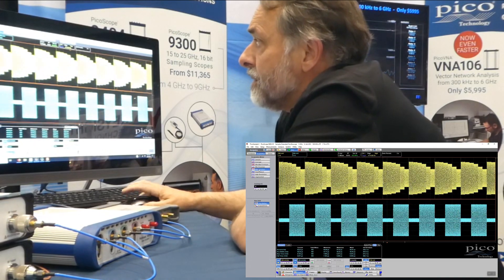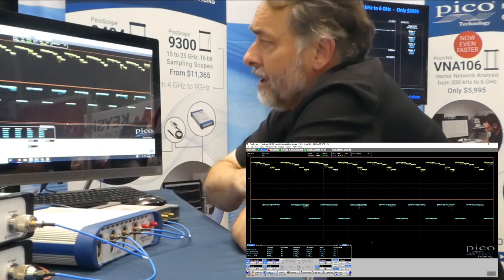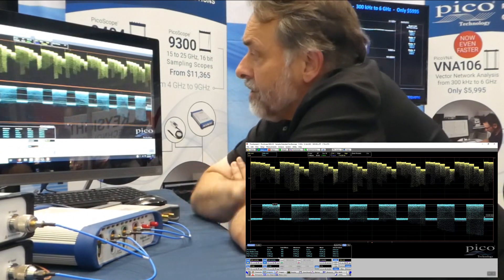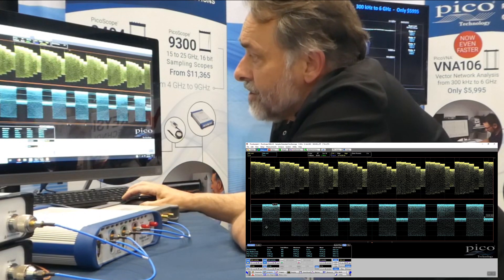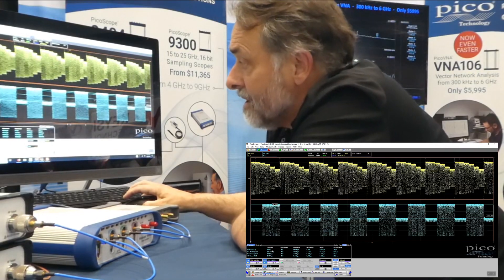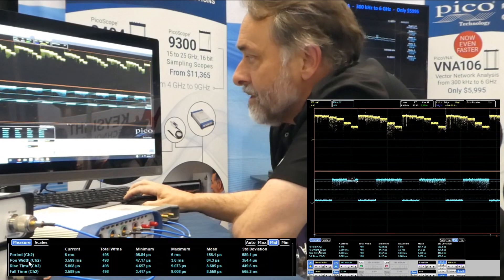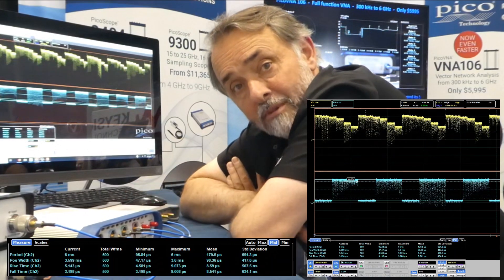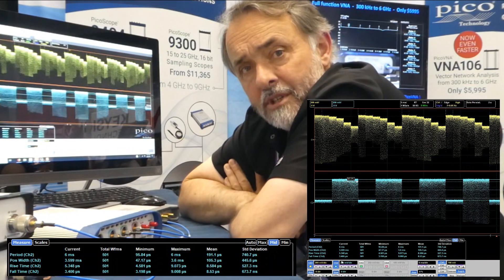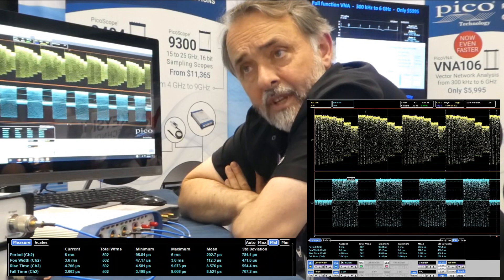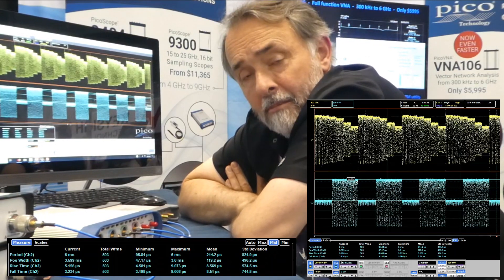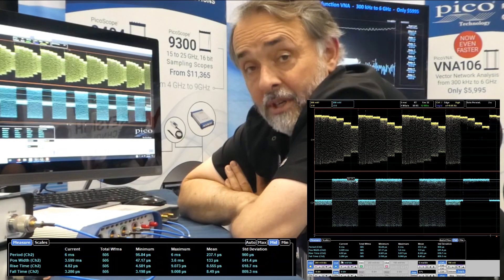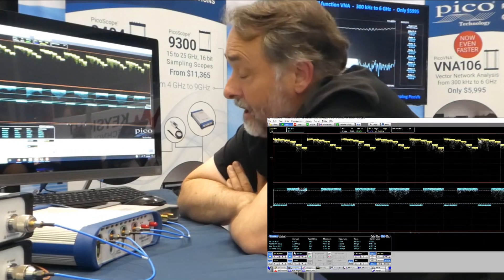What I can do is put this into envelope mode, and now the oscilloscope is tracing out the envelope of that carrier. You can see down in my measurement window on channel 2 I'm measuring the pulse width — a wave period of six milliseconds, a positive width of 3.6 milliseconds — and I've got rise and fall time of my envelope. That's quite an important characteristic of the 9404 SXRTO: the ability to make envelope measurements on RF carriers that lie within the bandwidth of the product. This might be Wi-Fi data or mobile phone data.